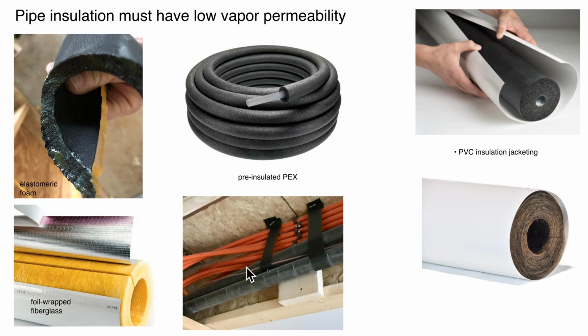The photo down here actually shows some of that pre-insulated PEX. You'll see some 1/2 inch PEX, aluminum PEX up here. This actually goes out to panel radiators for heating. But the 2 pieces of pre-insulated PEX are supported on nylon straps. And as I mentioned, these go right from a basement mechanical room right up to an air handler. And there are PVC shells that you can get as well.